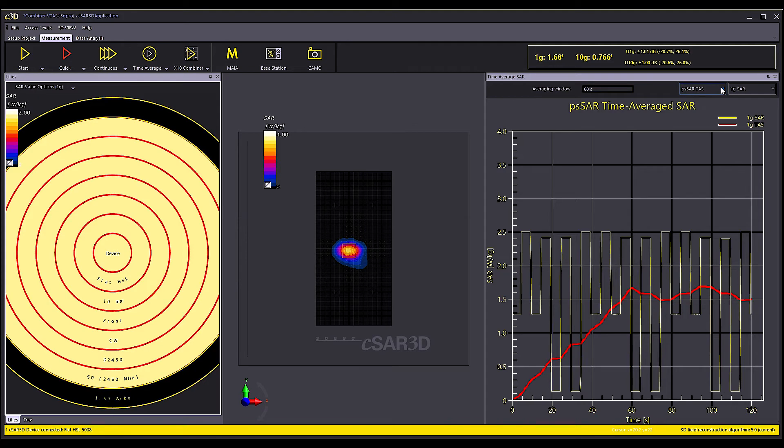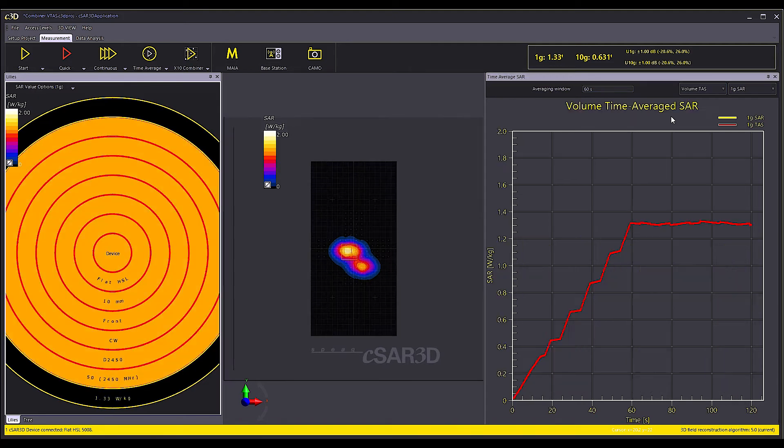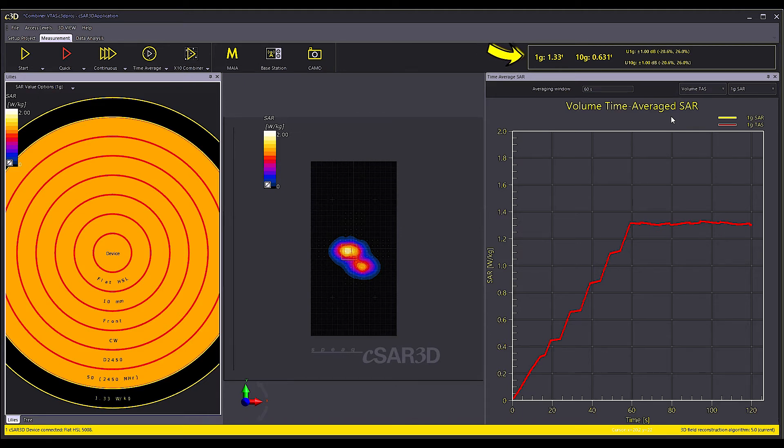Now I will reevaluate the same with volume TAS method. The final measured TAS values for this test configuration are 1.33 Watt per kg 1 gram and 0.63 Watt per kg 10 gram.